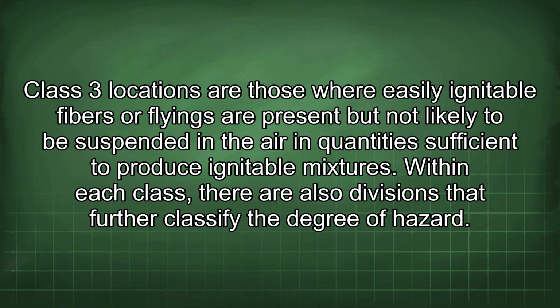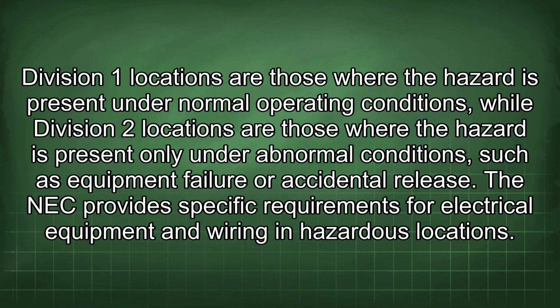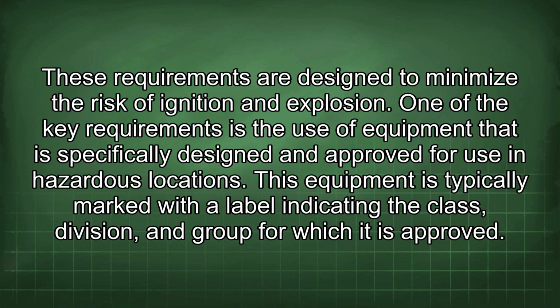Within each class, there are also divisions that further classify the degree of hazard. Division 1 locations are those where the hazard is present under normal operating conditions, while Division 2 locations are those where the hazard is present only under abnormal conditions, such as equipment failure or accidental release. The NEC provides specific requirements for electrical equipment and wiring in hazardous locations. These requirements are designed to minimize the risk of ignition and explosion. One of the key requirements is the use of equipment that is specifically designed and approved for use in hazardous locations. This equipment is typically marked with a label indicating the class, division, and group for which it is approved.